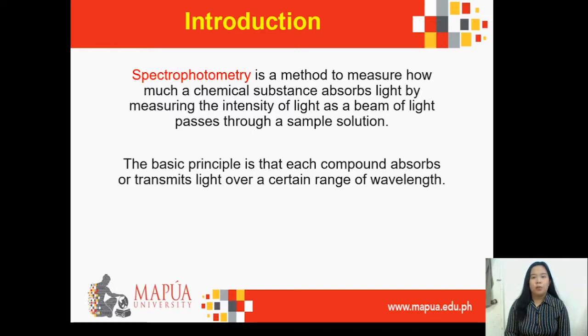The spectrophotometer is designed in a way that the liquid or sample is placed between the spectrometer and the photometer. The photometer measures the amount of light that passes through the sample and delivers a voltage signal to the display. If the absorbance of the light changes, the voltage signal also changes. The basic principle is that each compound absorbs or transmits light over a certain range of wavelength.